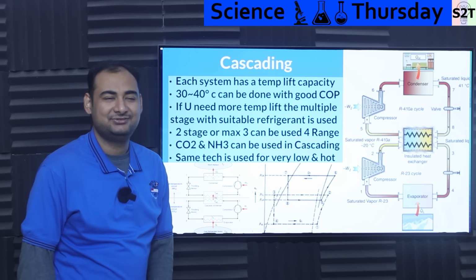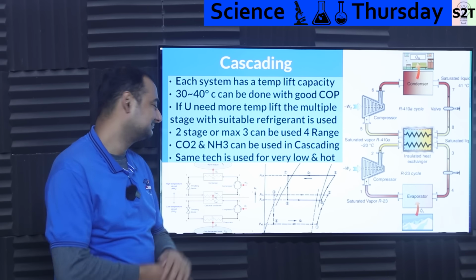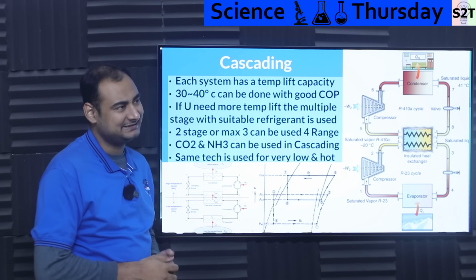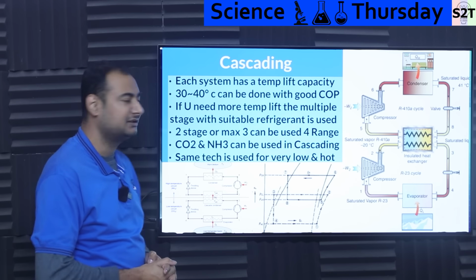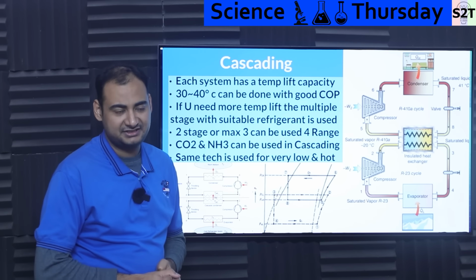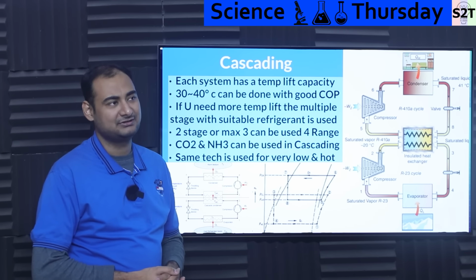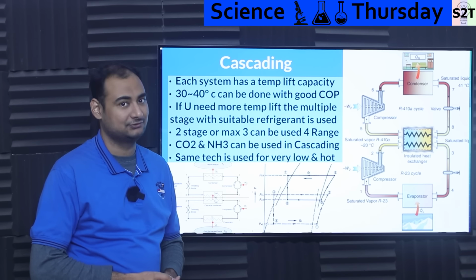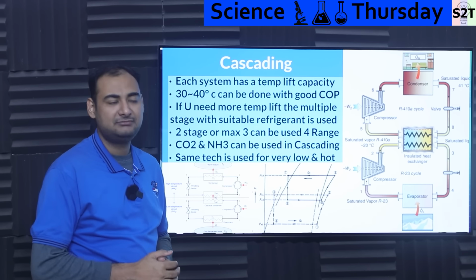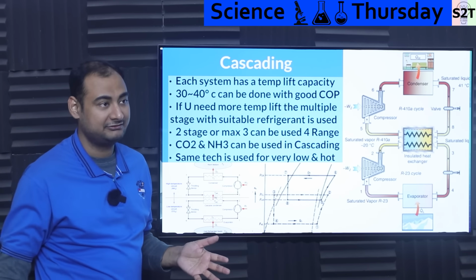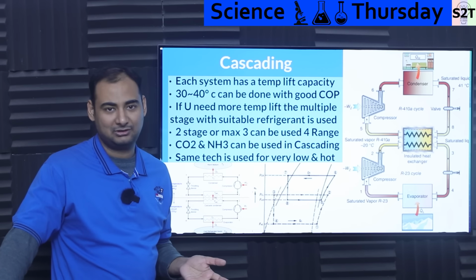But if you're like, do we really need that much? That's the sort of point to consider. So 2 is optimum, 3 is pushing it. For economic reasons, we generally do not consider a heat pump logical if it starts to reach 3 or 4 stages. 2 is awesome, 1 is reasonable but unlikely to pull off — even in Indian heat, you can't pull off everything in 1 loop.